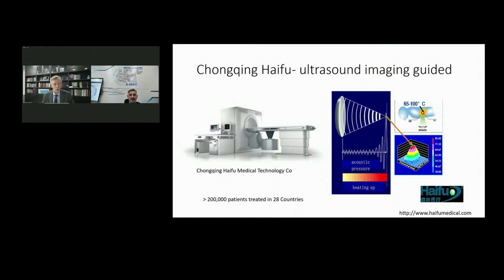Okay, so I was asked to talk a little bit about the history of the devices. And the first device that was used, and is still used, is the Chongqing HIFU device. It has a spherically curved transducer with a single focus and uses very high amplitudes to generate thermal damage. It's guided by ultrasound, so there is no real online monitoring of the temperature. But it has been very effective and used in treating over 200,000 patients.